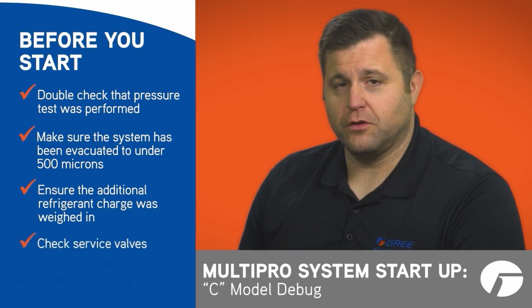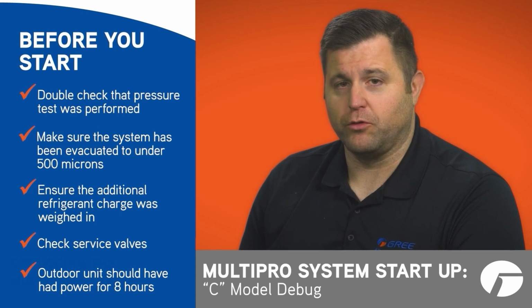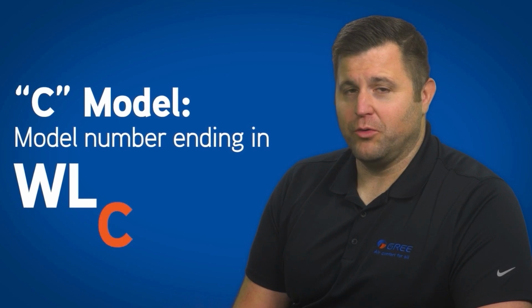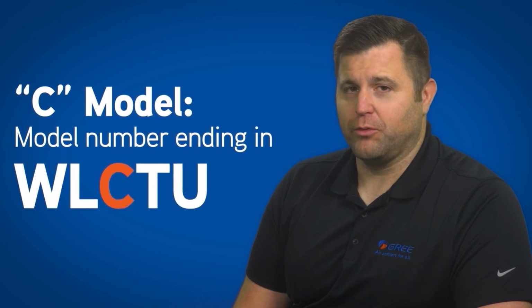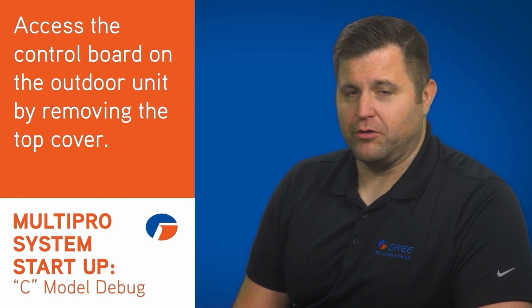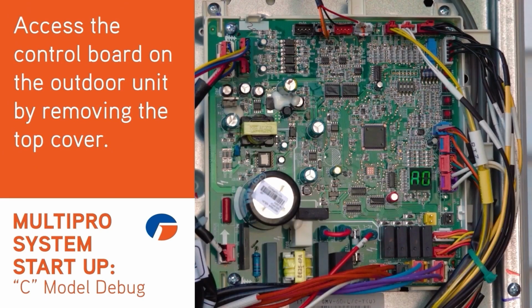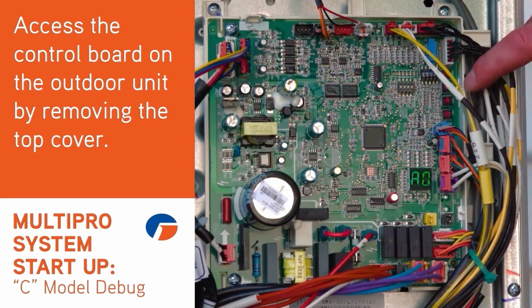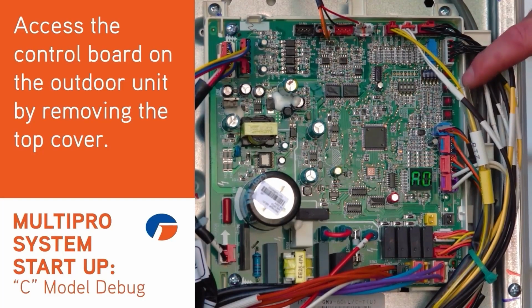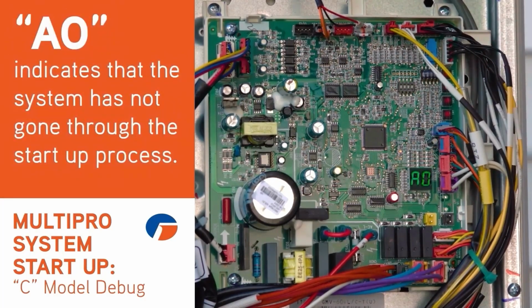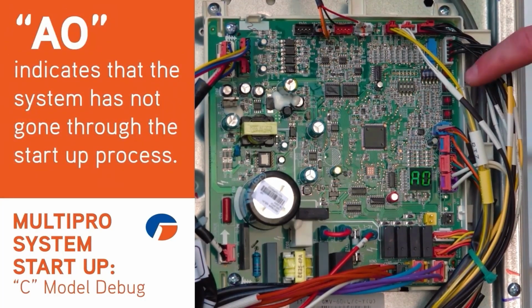Also ensure that the service valves are open on the outdoor unit and that the power has been applied to the outdoor unit for the recommended 8 hours. If you have a C model as indicated by the model number ending in WLCTU, you'll perform the following steps. Access the control board of the outdoor unit by removing the top cover. There you'll find a 2-digit display and 4 buttons labeled SW1 through SW4. This display should read AO, as should all indoor units and wired controllers.